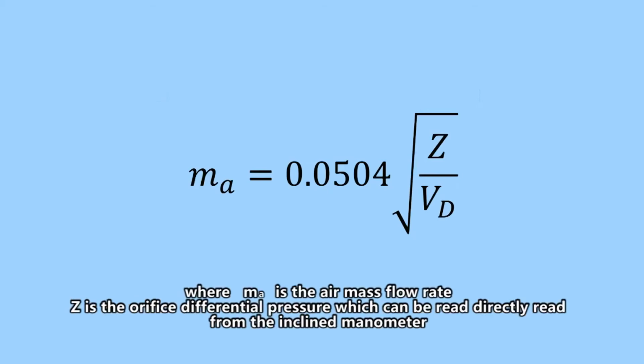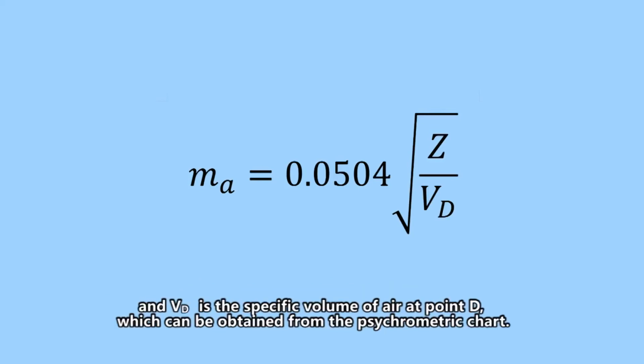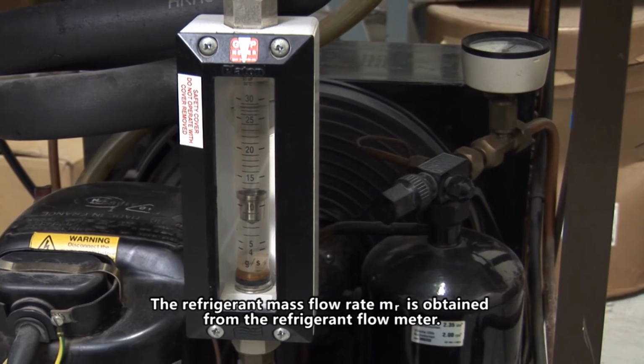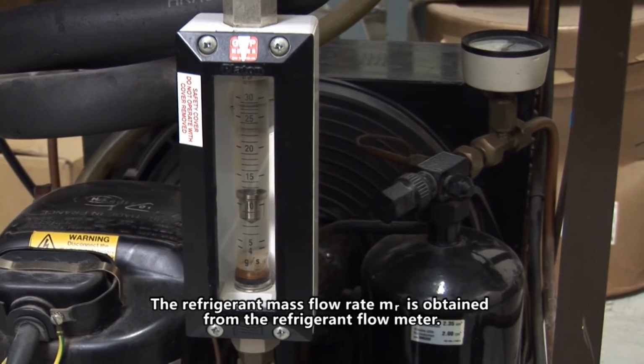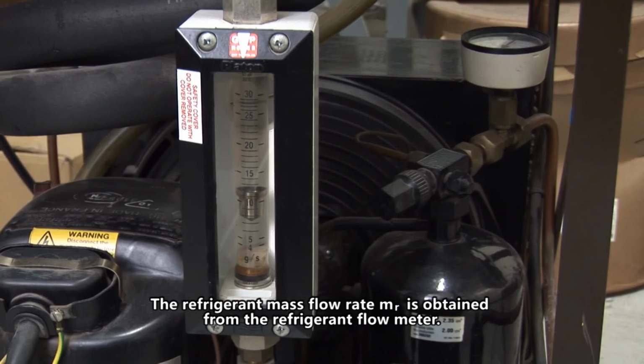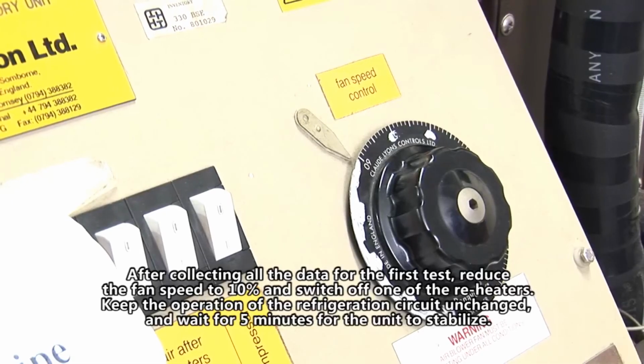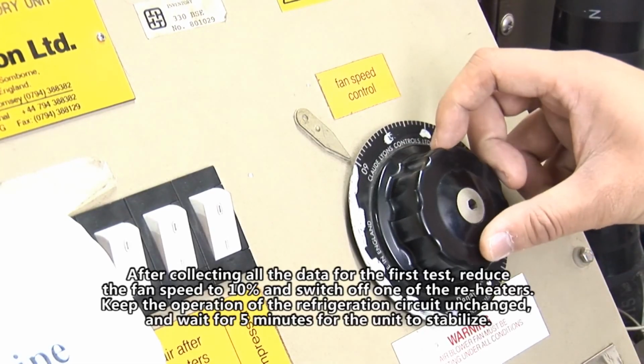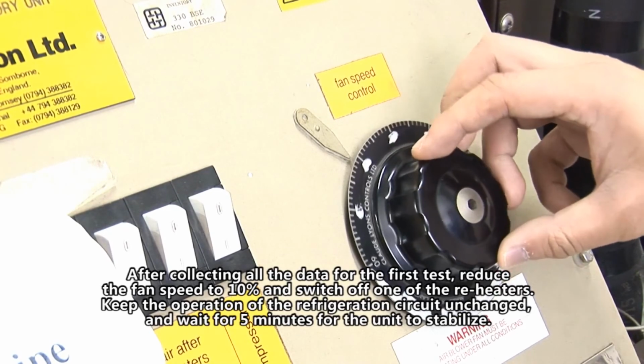The air mass flow rate is obtained from the incline manometer reading using this equation, where M subscript A is the air mass flow rate, Z is the orifice differential pressure, which can be read directly from the incline manometer, and V subscript D is the specific volume of air at point D, which can be obtained from the psychrometric chart. The refrigerant mass flow rate, M subscript R, is obtained from the refrigerant flow meter.